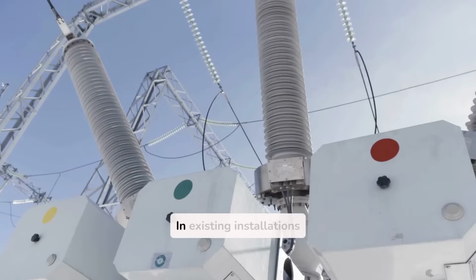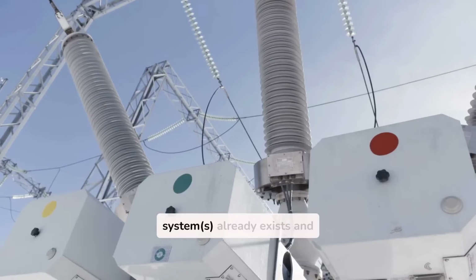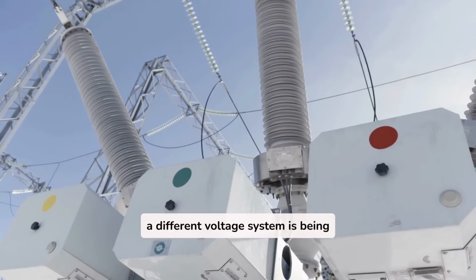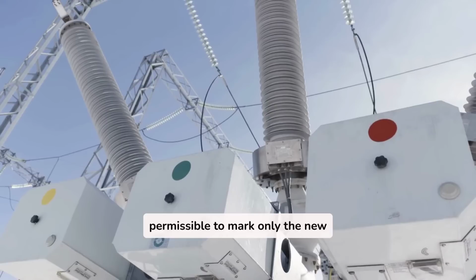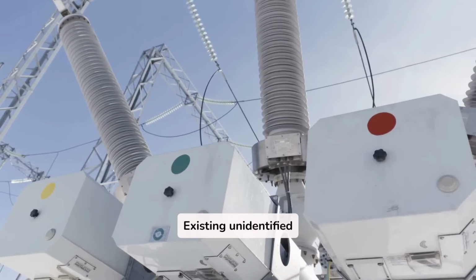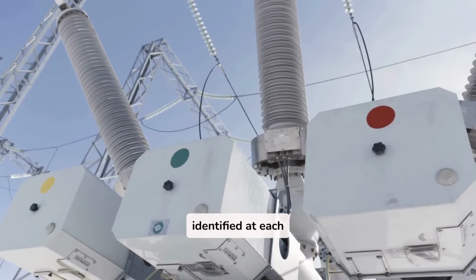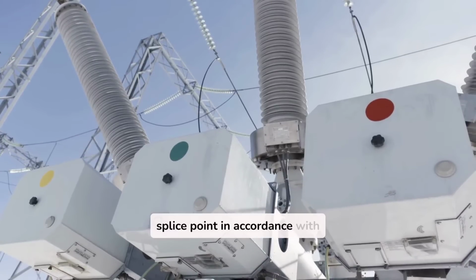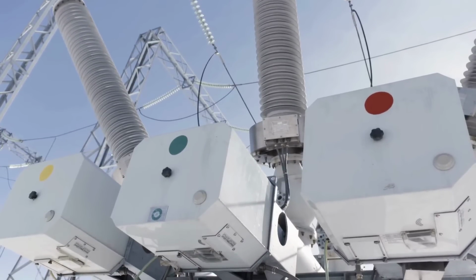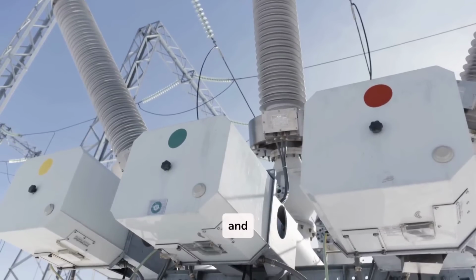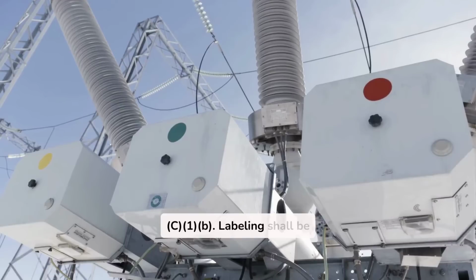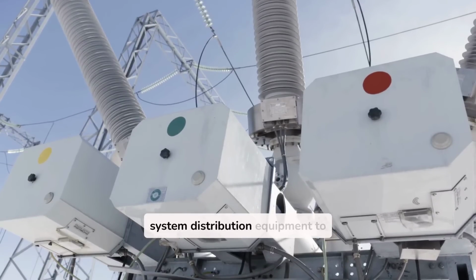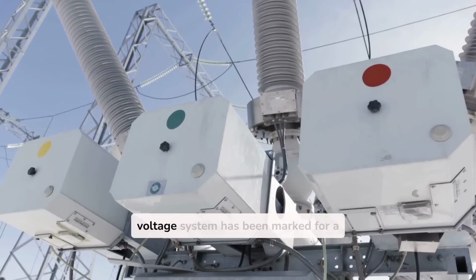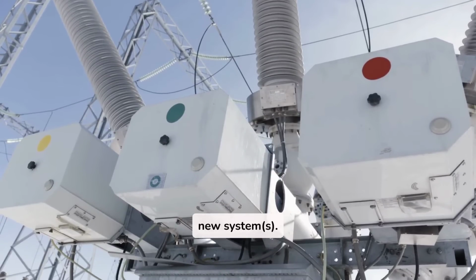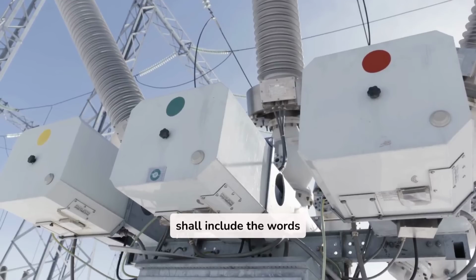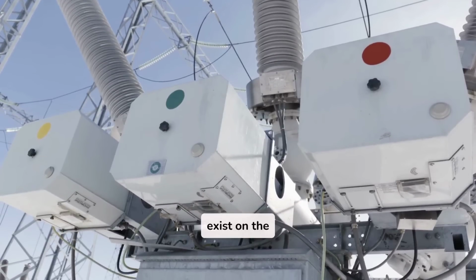Exception. In existing installations where a voltage system already exists and a different voltage system is being added, it shall be permissible to mark only the new system voltage. Existing unidentified systems shall not be required to be identified at each termination, connection, and splice point in accordance with 210.5(C)(1)(a) and (C)(1)(b). Labeling shall be required at each voltage system distribution equipment to identify that only one voltage system has been marked for a new system. The new system labels shall include the words "other unidentified systems exist on the premises."